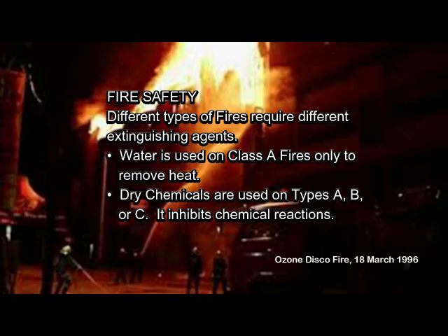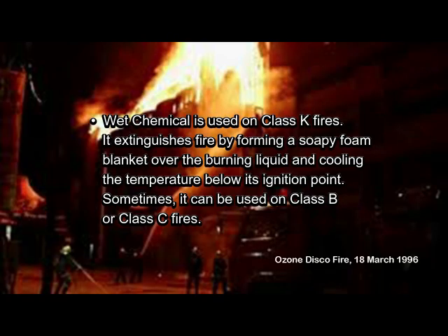Water is used on Class A fire only, to remove heat. Dry chemicals are used on types A, B, or C. It inhibits chemical reactions. Wet chemical is used on Class K fires. It extinguishes fire by forming a soapy foam blanket over the burning liquid and cooling the temperature below its ignition point. Sometimes, it can be used on Class B or Class C fires.